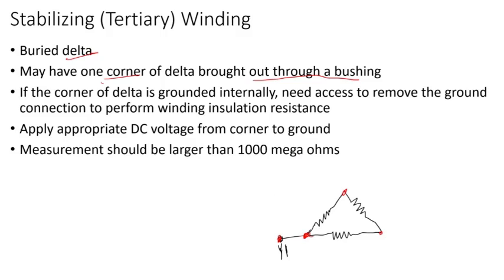Then when you want to perform this test, all you need to do is remove that jumper from this bushing to ground. You don't have to drain the transformer or do any extensive work. This is the best option because if it's grounded internally you have to access that grounding jumper and remove it.